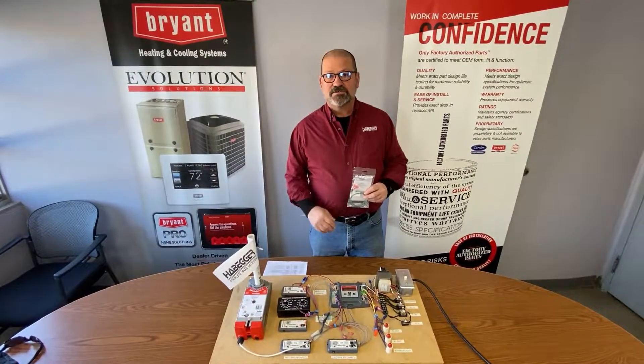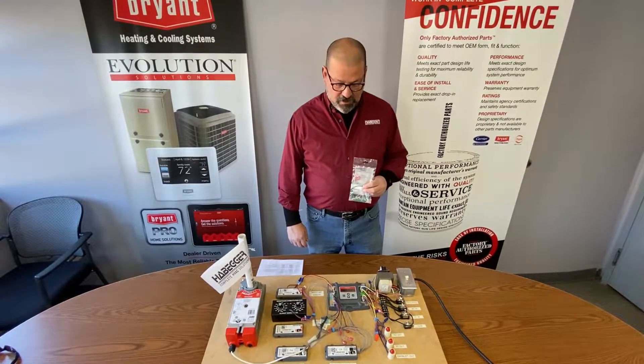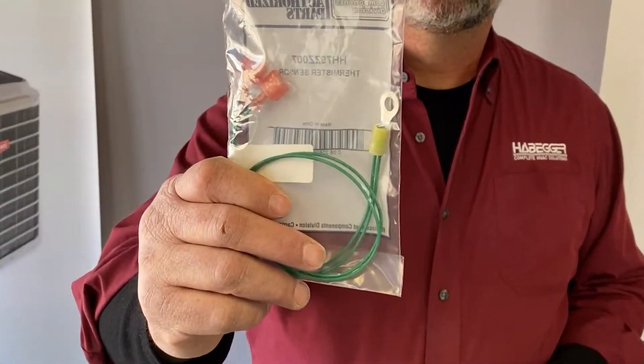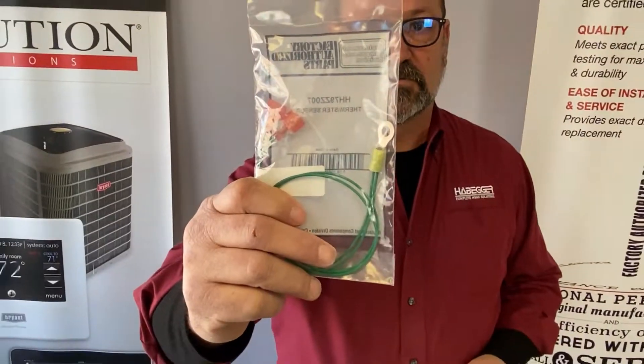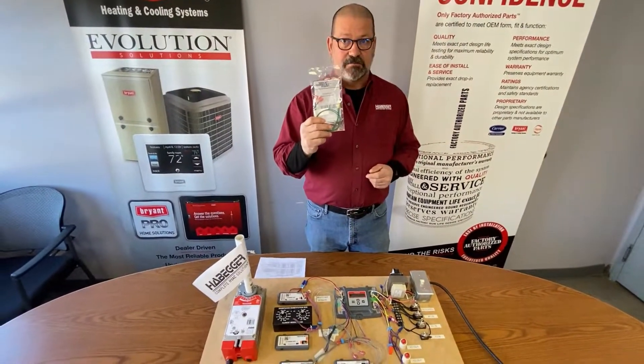Hi, my name is Ray with the Habegger Corporation. I just wanted to go over the Jade controller, the W7220 economizer control. Just a couple of quick things. One, they're shipped with this thermistor. It looks kind of like a ground, but it's actually a thermistor for temperature. This can be used for your mixed air temperature or your outdoor air temperature.